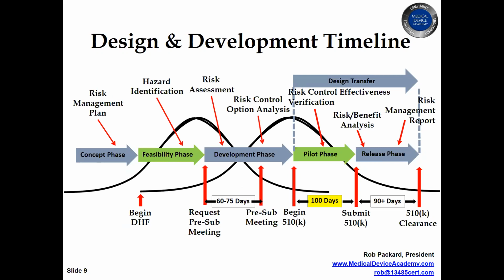But in theory, the way it's supposed to work is you come up with an idea for a product, and that's in the concept phase, and that's when you create your design plan and your risk management plan. And when you approve that plan is when you're supposed to start your DHF. What do most companies do? They wait until they're almost ready to start their verification validation testing, and that's when they start their DHF. So there's a lot of work that has to be retroactively documented. Is that bad? No. It's just less than ideal. That means you get some retroactive work to document. And retroactive documentation is always a little bit more challenging than if you had done it while you were doing it. It's always easier to document while you're in the activity than after the fact.